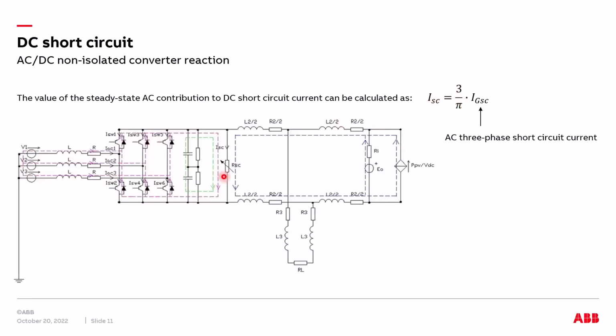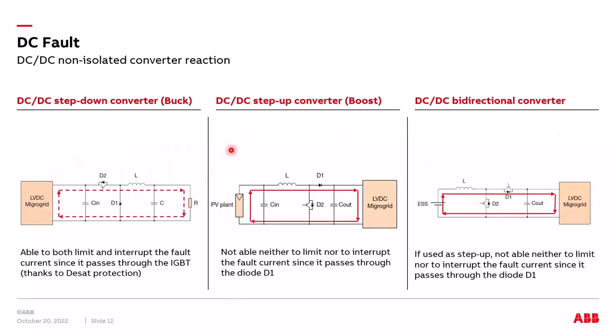And as you can see from this formula, practically this DC contribution coming from the AC grid is equal to the prospective AC short circuit current contribution that we have at the input of our AC/DC converter. For example, if on the AC side of the converter we have a prospective short circuit current of 50 kA, practically this value of current contribution is the same on the DC side. So we need some suitable protective devices in order to be able to detect and interrupt this short circuit.